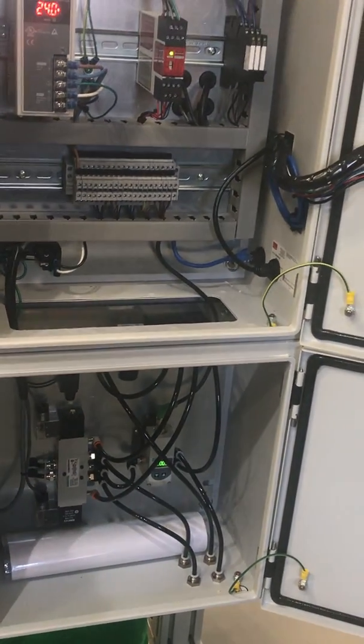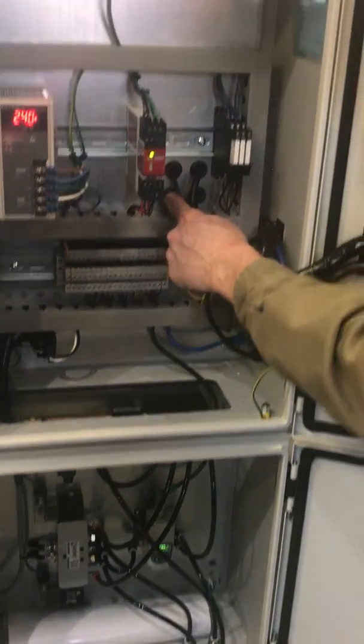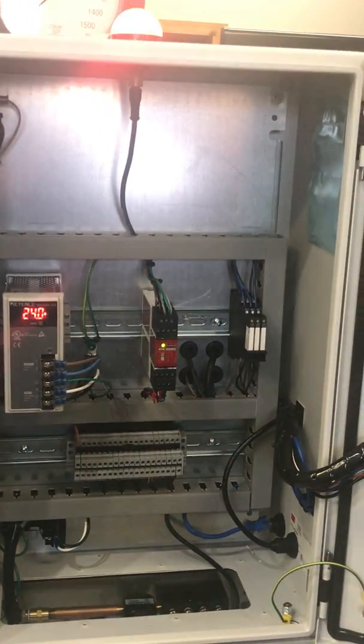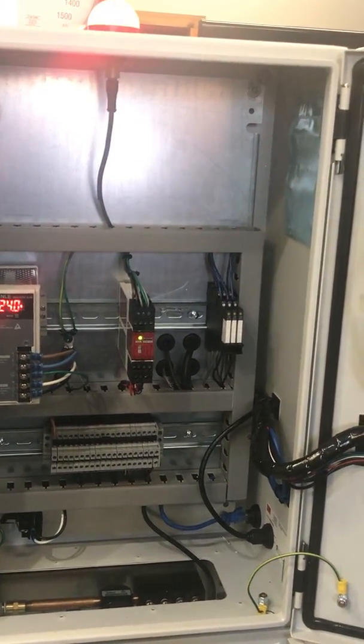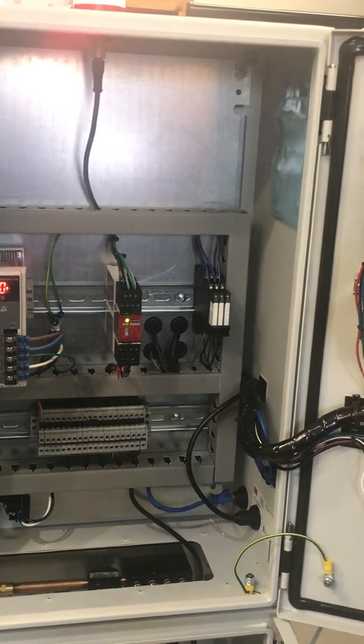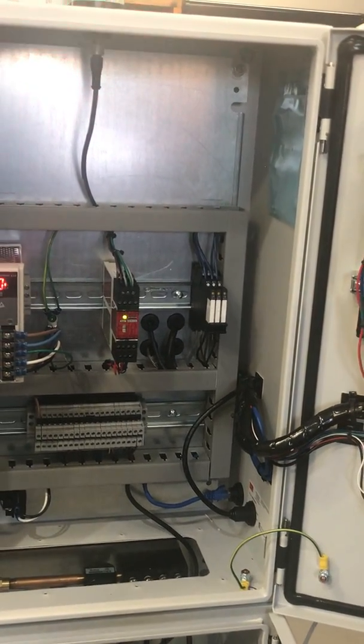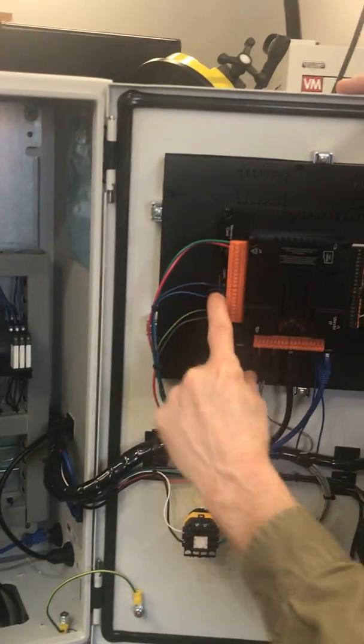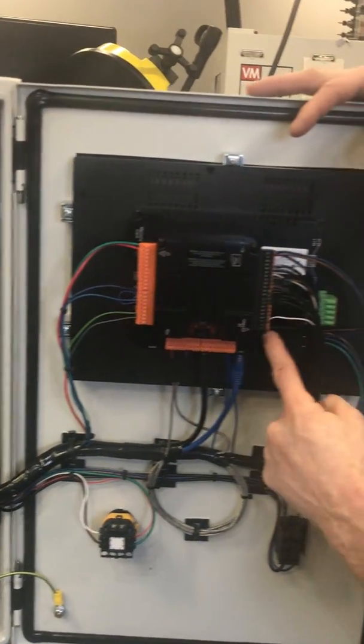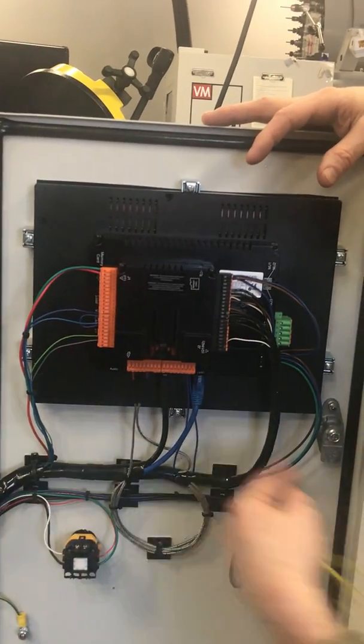Yeah, you have the 2 thermocouples. One of them is coming in through here, and another one is coming in through there. Thermocouple wires, those are your analog inputs for thermocouples. Here is your position sensor, and there's your pressure transducer. So there are 2 more analog inputs: 1, 2, 3, 4 analog inputs. And then these are your outputs, so like turn on the light, turn on the fans, turn on the cabinet light, open and close this valve, turn on these things.